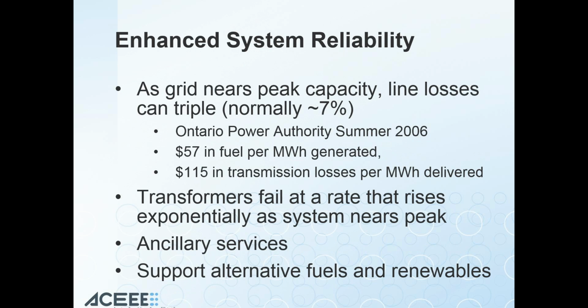Another benefit of distributed generation—and CHP can be a form of distributed generation—is that it reduces line losses at peak. We traditionally think of line losses as around 7%, but that's under normal operating conditions. When you start reaching the capacity of a transmission system, your losses, what an electrician would call an I²R loss or friction loss, increase exponentially—it could increase to three times that 7%.